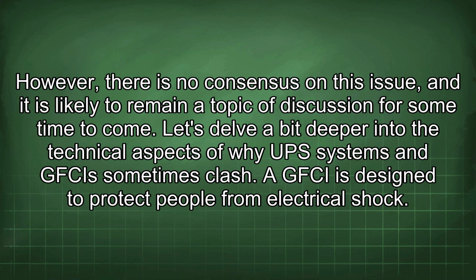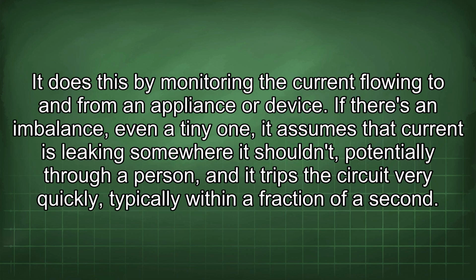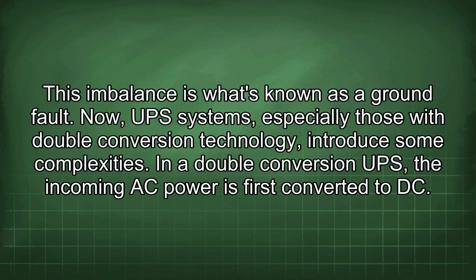Let's delve a bit deeper into the technical aspects of why UPS systems and GFCIs sometimes clash. A GFCI is designed to protect people from electrical shock. It does this by monitoring the current flowing to and from an appliance or device. If there's an imbalance, even a tiny one, it assumes that current is leaking somewhere it shouldn't, potentially through a person, and it trips the circuit very quickly, typically within a fraction of a second. This imbalance is what's known as a ground fault.